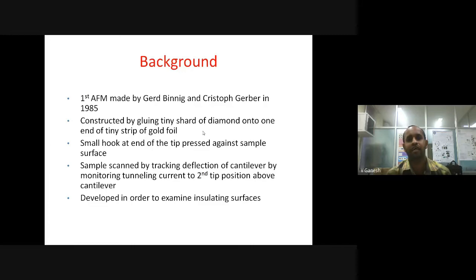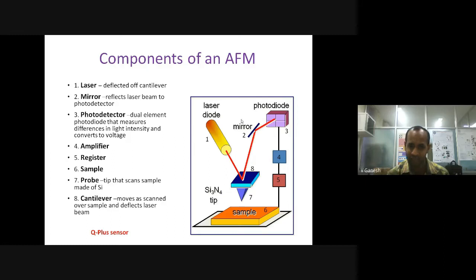I will explain again. This is the cantilever, which is nothing but a polymer. At the end of the cantilever, one can attach silicon nitride, silica, or silicon diamond as a tip. Usually the backside of the cantilever is coated with gold, so that when you shine laser light on top of it, by looking at the intensity change, one can correlate the oscillation change - the force constant that exists between the sample substrate and the probe, which is nothing but silicon nitride in this case.